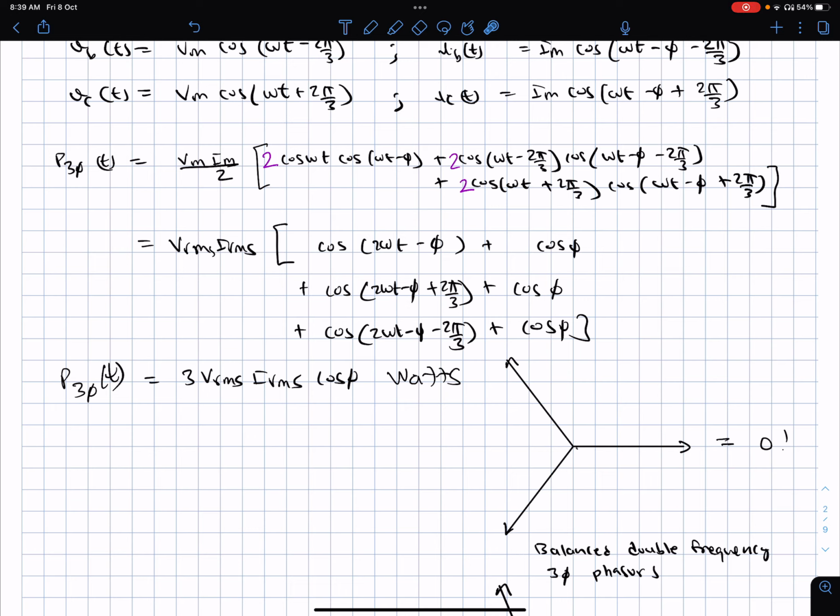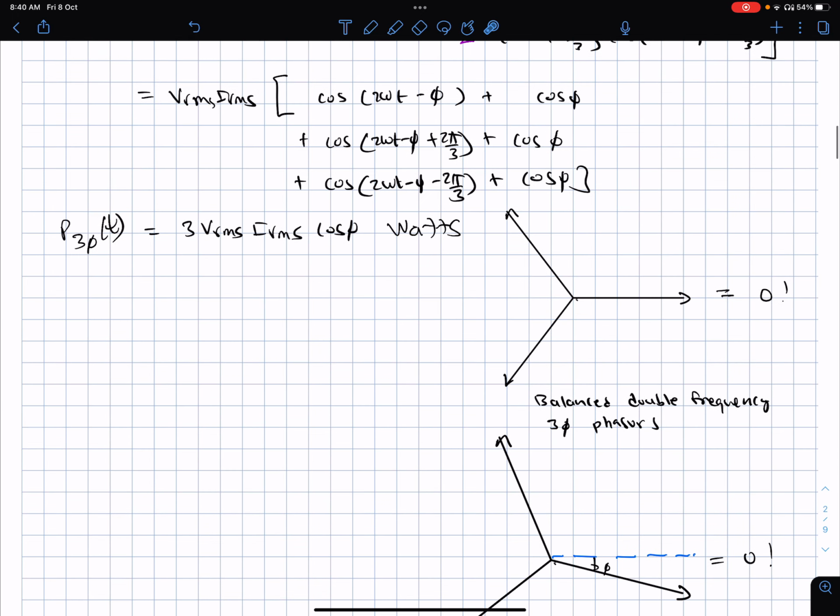So, what is done is that utilities carefully, by choosing some rule, make sure that on each phase, when they aggregate it at the distribution system level and transmission system level, by the time the aggregation happens, each of the phases has become almost balanced, and therefore the generators which are connected behind the transmission system, so to say, see a very balanced loading condition and therefore don't face the problems of pulsating power.